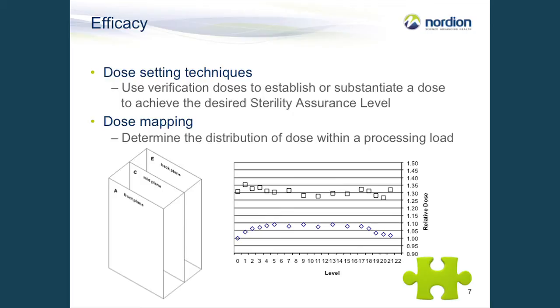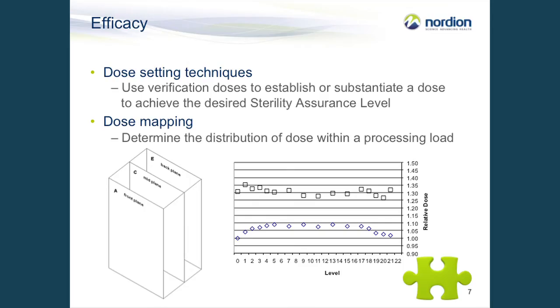This graph shows a typical set of dose mapping results. In this case, the minimum and maximum dose from each of several vertical levels in the product stack are plotted on a relative scale. The minimum dose is set to 1, and you can see that the maximum dose here is about 1.35 times the minimum. Dose mapping is used to ensure that at least the minimum dose is achieved throughout the entire product stack. So the dose mapping results are correlated to the irradiation conditions that meet this minimum requirement.